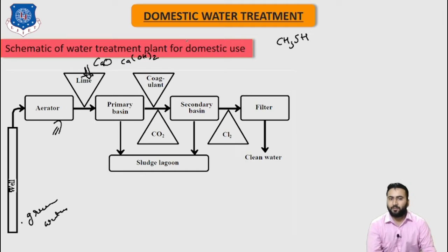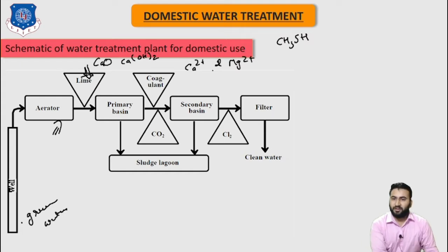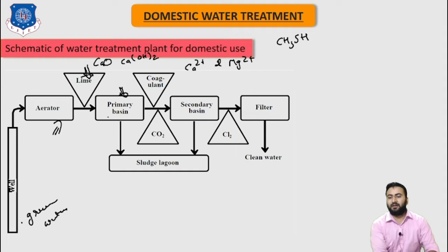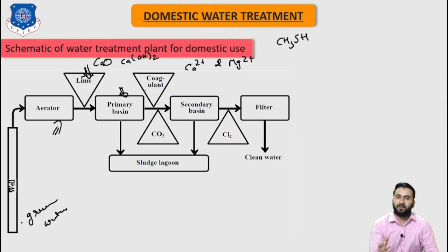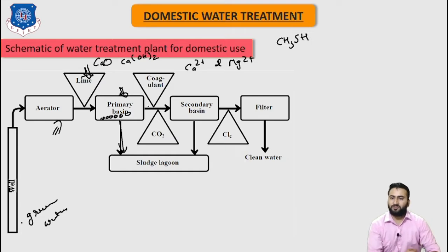After addition of lime, the pH rises and results in formation of precipitate containing the hardness ions Ca²⁺ and Mg²⁺. This precipitate settles from the water in the primary basin. Much of the solid material remains in suspension and requires the addition of coagulants such as iron trisulfate and aluminum sulfate, which form gelatinous metal hydroxides that settle down and collect colloidal particles for sludge.